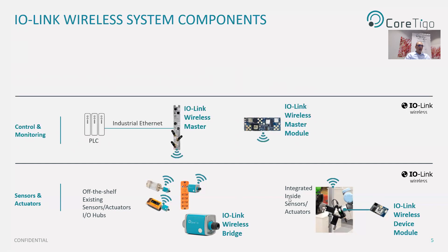Moving up, we can see the IO-Link Wireless masters, which enable the communication between the devices and the PLC at the OT level — for example, via industrial Ethernet communication such as EtherNet/IP or PROFINET — but also to any enterprise and cloud applications at the IT level, for example via MQTT or OPC UA. The master is an off-the-shelf IP67 device, with an industrial Ethernet interface and the ability to communicate with up to 40 IO-Link Wireless devices per standard specification.